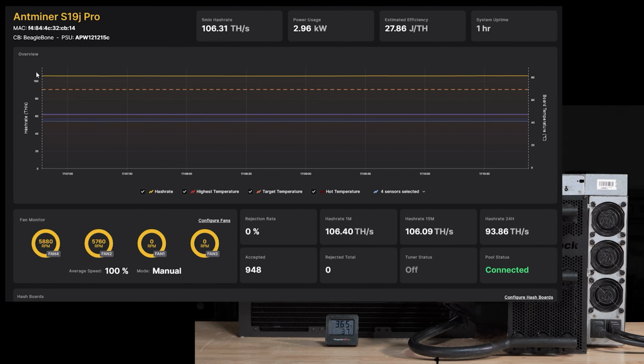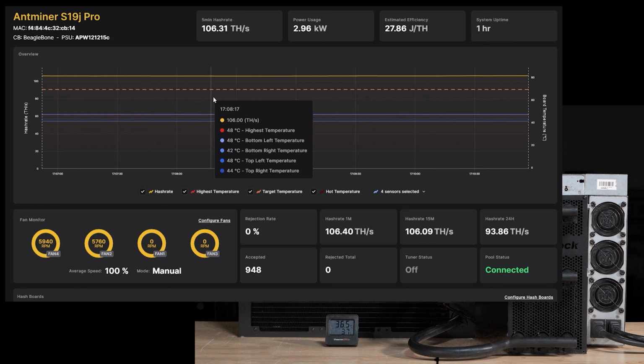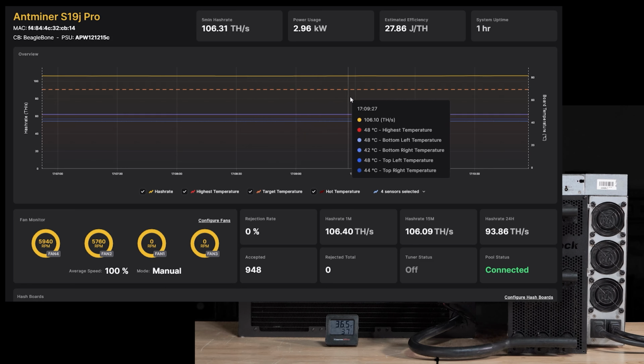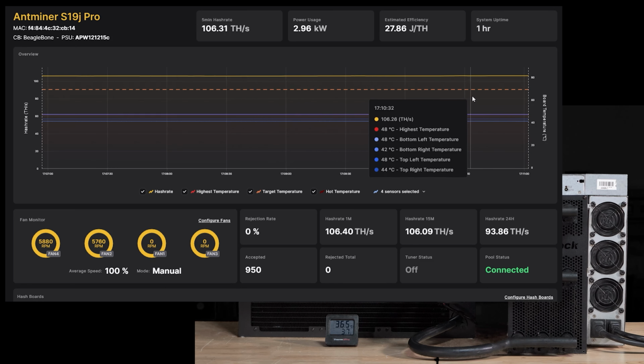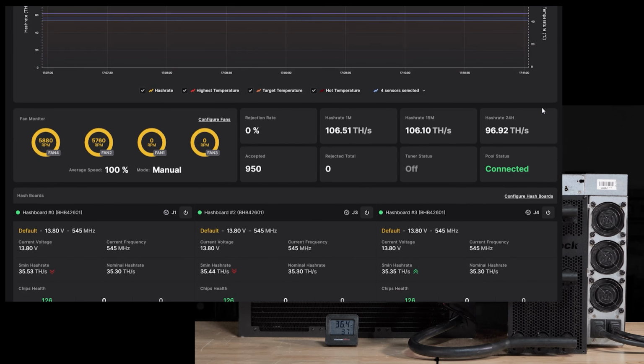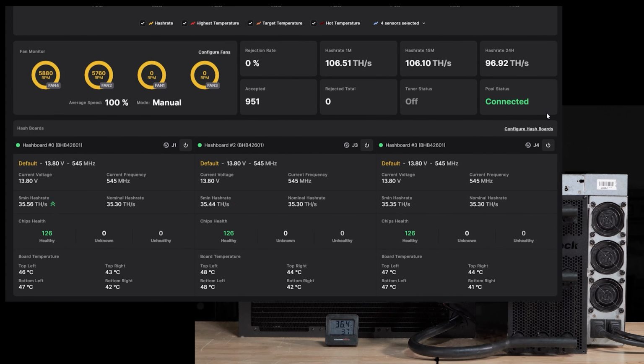As we get to the end of the test, you'll see that the maximum temperature inside this unit is only 48 degrees Celsius, while the ambient temperature is 36.5 degrees Celsius, which is over 97 degrees Fahrenheit. This is an extremely cool temperature for such a hot environment. And the difference in temperature between our hottest and coldest sensors was only 7 degrees Celsius.